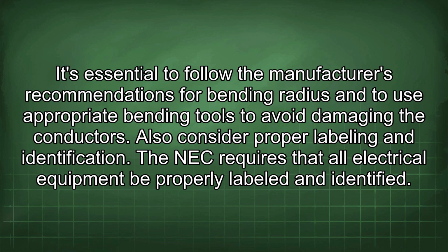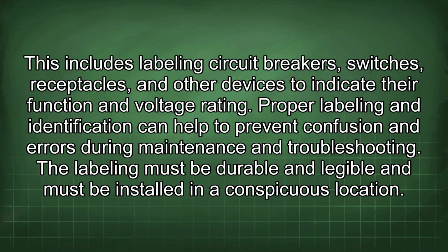The NEC requires that all electrical equipment be properly labeled and identified. This includes labeling circuit breakers, switches, receptacles, and other devices to indicate their function and voltage rating. Proper labeling and identification can help to prevent confusion and errors during maintenance and troubleshooting. The labeling must be durable and legible and must be installed in a conspicuous location.